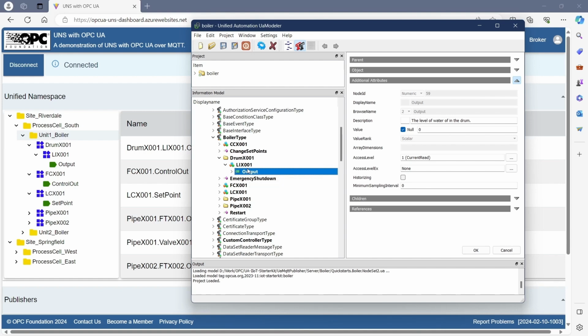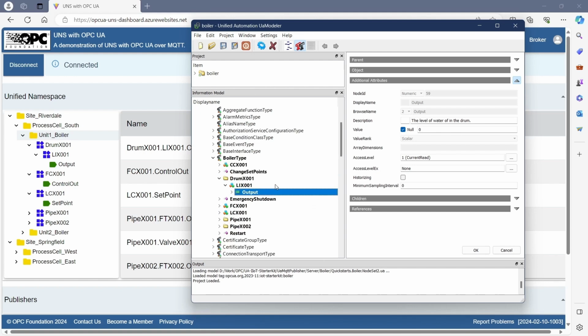For example, let's say a machine installed in a factory provided maintenance information that the machine vendor needed to access. Yet the same vendor should not be given access to data for process information belonging to the factory operator. In OPC UA, a single publisher can publish two different views of the device to two different topics to resolve these kinds of conflicts.